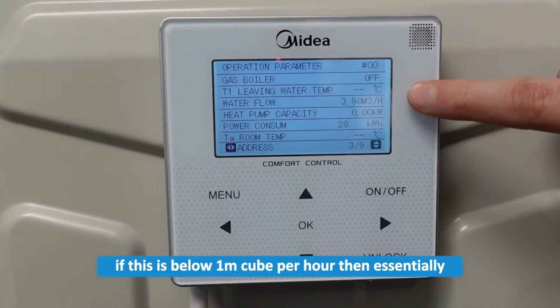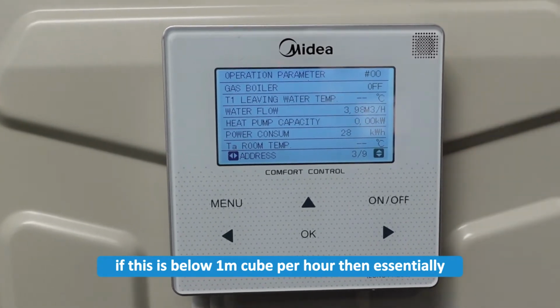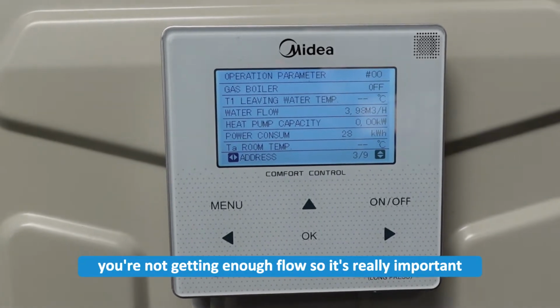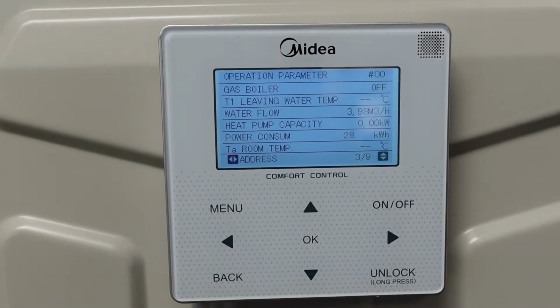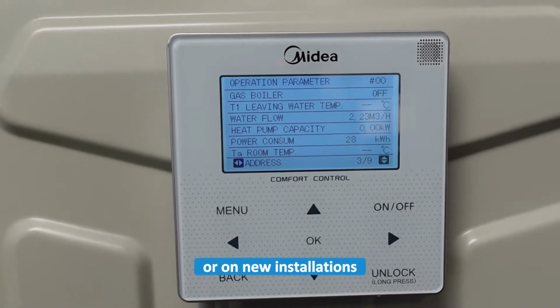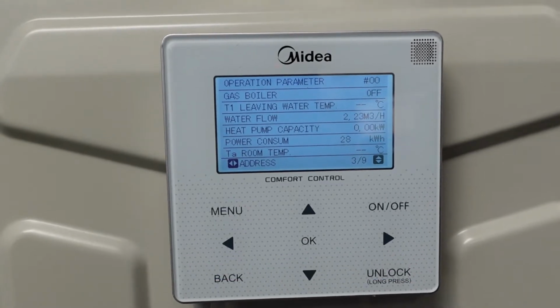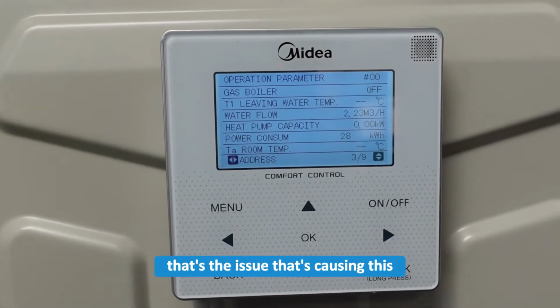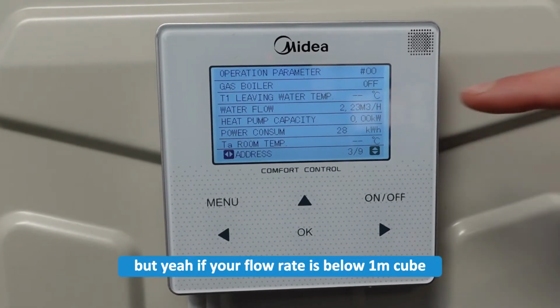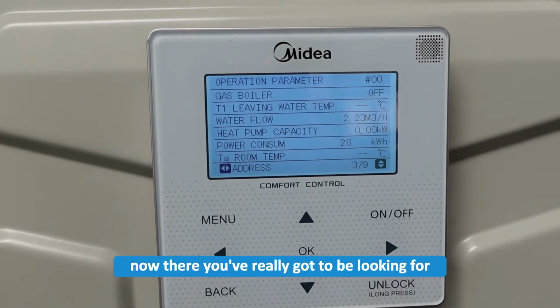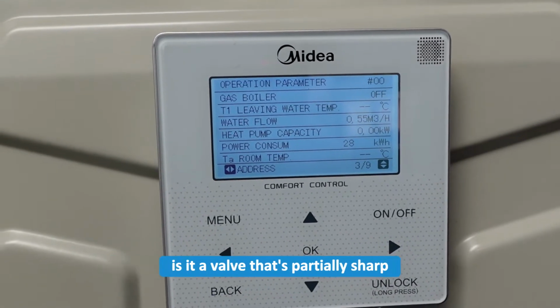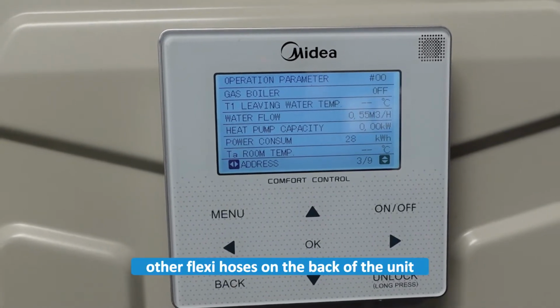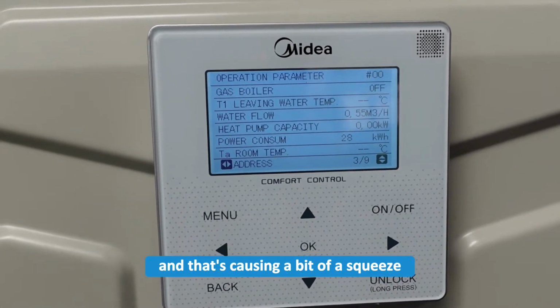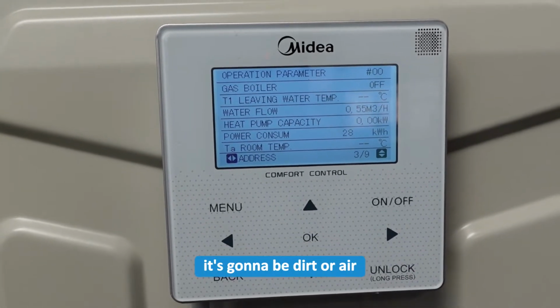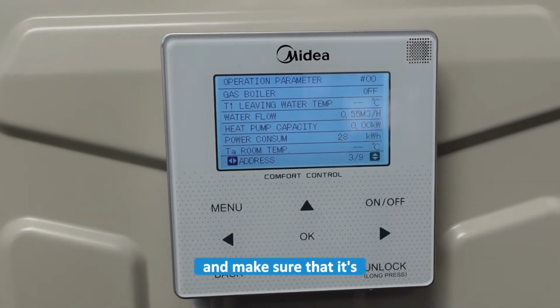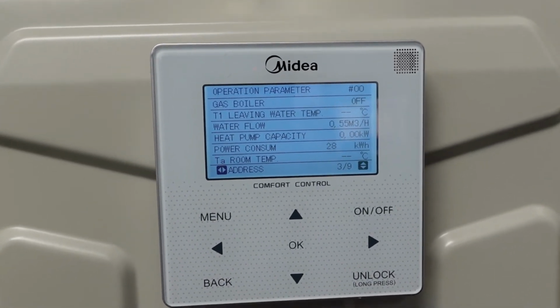If this is below 1 meters cubed per hour, then essentially you're not getting enough flow. So it's really important that you are checking for restrictions in the pipework, or on new installations, if you haven't done your pipe sizing correctly, then that might be the issue that's causing this. But yeah, if your flow rate is below 1 meters cubed an hour, you've really got to be looking for what's causing that restriction in the pipework. Is it a valve that's partially shut? Are the flexi hoses on the back of the unit slightly kinked and that's causing a bit of a squeeze? But yeah, if it's not that, it's going to be dirt or air. So just make sure you're really checking and make sure that it's all clean and clear.